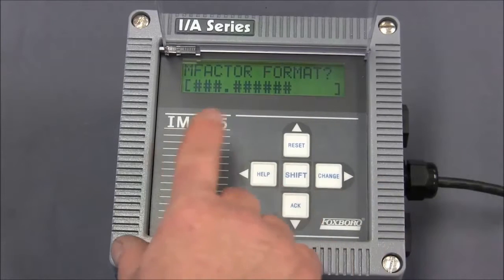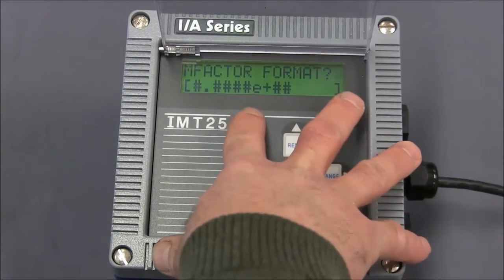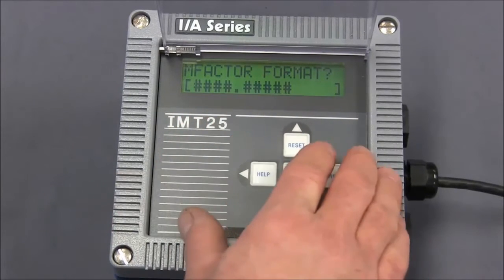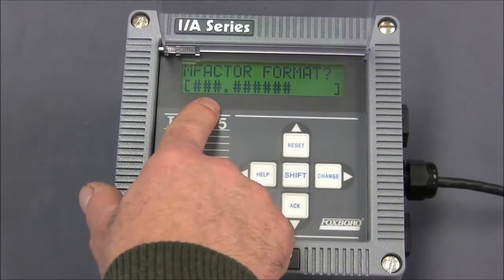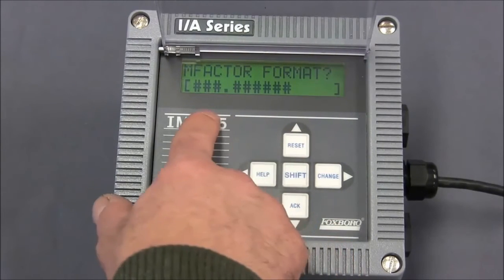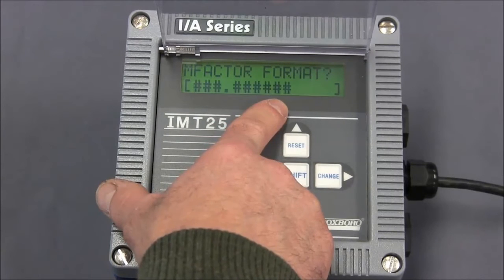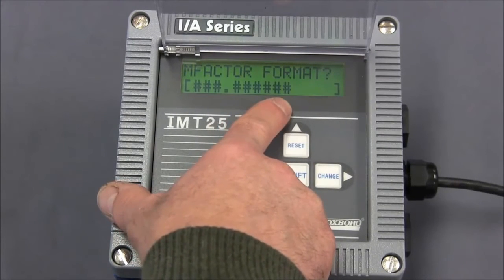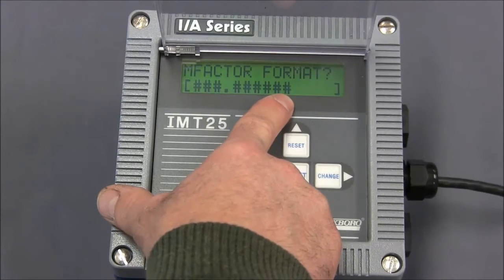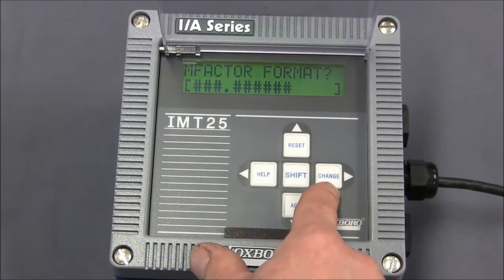When we do that, the entire line will begin flashing. Our choices are exponential format, four positions to the left of the decimal point and five positions to the right, or three positions to the left and six positions to the right of the decimal point. So for us, we'll leave this at three positions to the left and six to the right. If you had a calibration factor that had more than six positions to the right of the decimal point, you would have to round it to the last six positions. So we're going to accept this format, and to accept it, we simply hit the change key.